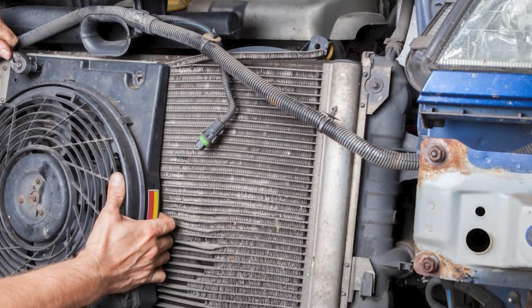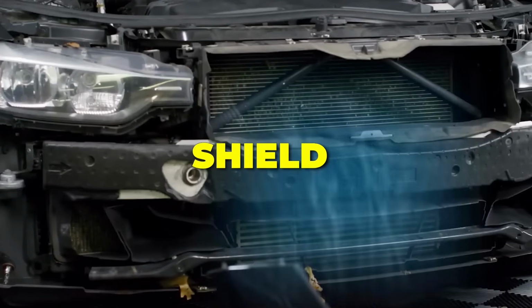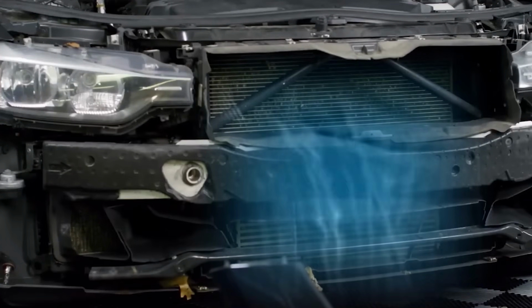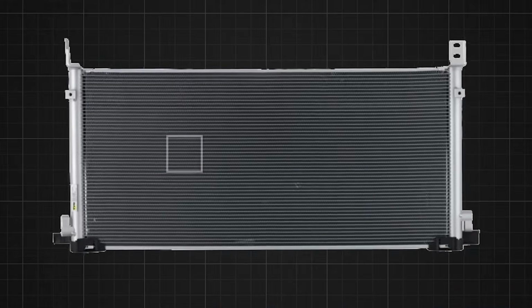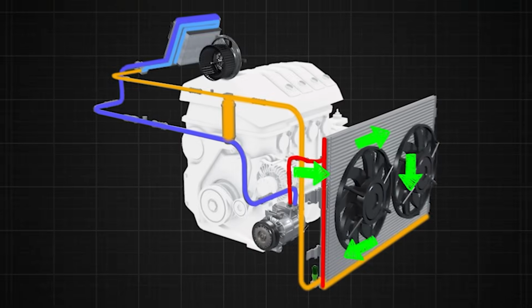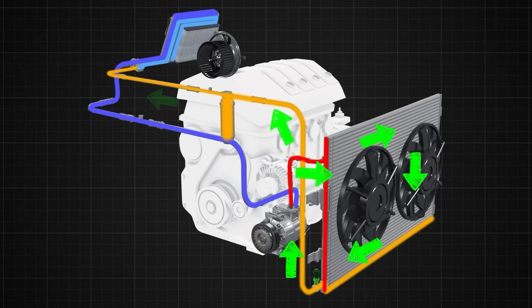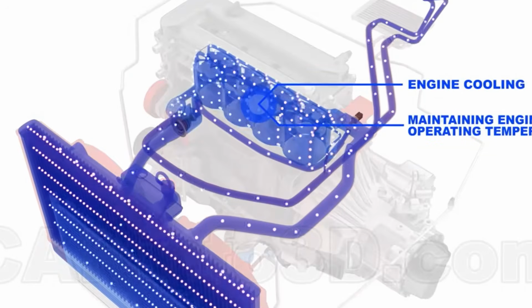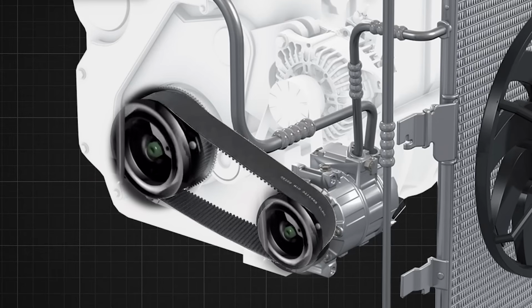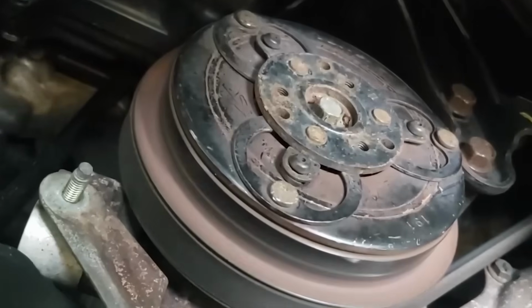Because of its location, the condenser acts as a shield that constantly collects bugs, road grime, leaves, and bent aluminum fins, all of which act as an insulative blanket. If the condenser cannot shed heat efficiently, then the system head pressures skyrocket, which forces the compressor to work at elevated loads and severely lowers its overall cooling capacity.